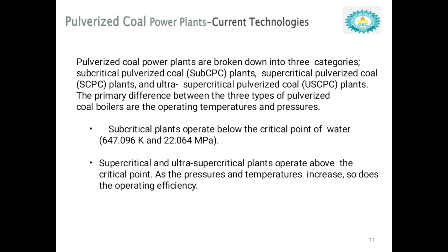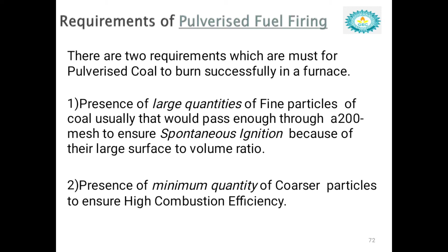And what are the requirements of pulverized fuel firing? We have two requirements majorly. One is the presence of large quantities of fine particles of coal, usually passing through 200 mesh, to ensure spontaneous ignition because of their large surface to volume ratio. And the second one is the presence of a minimum quantity of coarser particles to ensure high combustion efficiency.